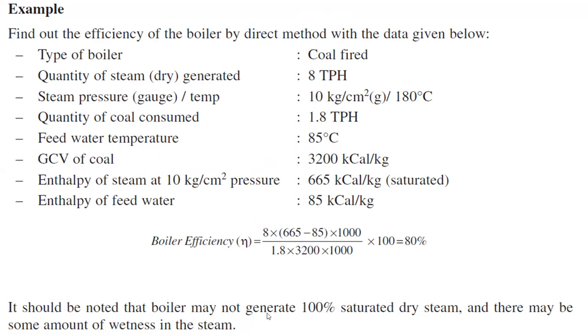Substituting the values: the numerator is 8 tons/hr of steam × (665 − 85) kcal/kg × 1000, and the denominator is 1.8 tons/hr × 3200 kcal/kg × 1000. Calculating this gives a boiler efficiency of 80%.